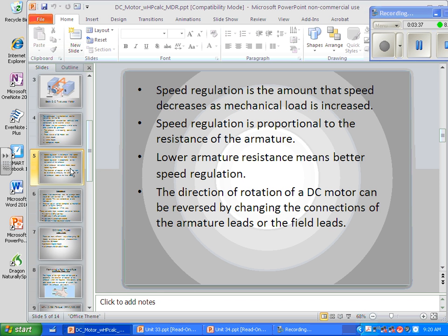Why would we want to reverse the armature instead of the field winding? Because the windings in the armature are very, very small, so there's very little magnetic field to create residual magnetism. Whereas the stator winding is a really big winding that creates a lot of residual magnetism — it might reverse and run at a different speed than it should because of that residual magnetism.